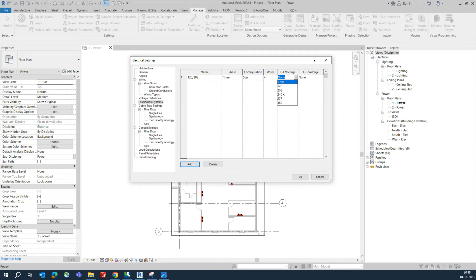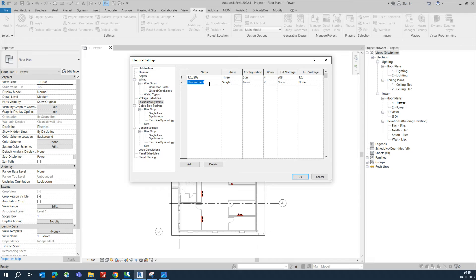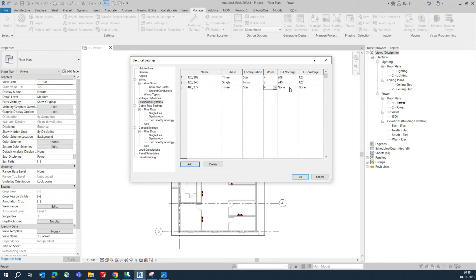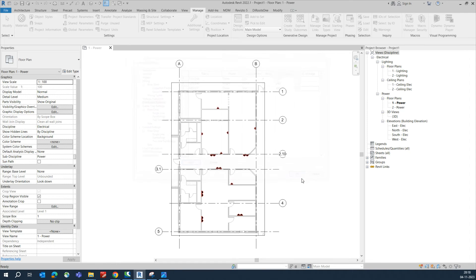Add a 120V entry. Then add a 120/240V single-phase entry: set it to single phase, 3 wires, 240V line-to-line and 120V line-to-neutral. Also add a 480/277V three-phase entry: 3-phase, 4 wires, 480V line-to-line and 277V line-to-neutral. Once set up, click OK.